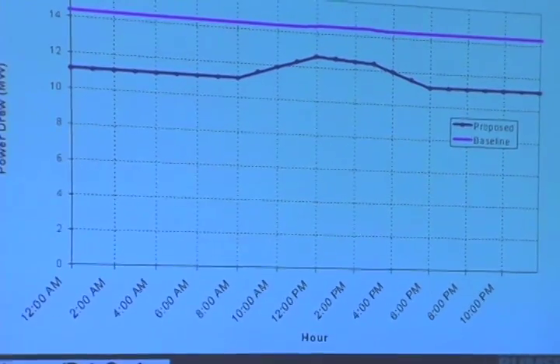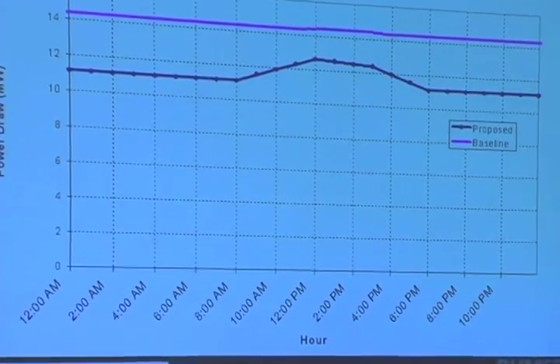Going back to the chiller energy model, the graph you had, did you look at chilled water storage or ice storage to use off-peak power for the cooling? So the question was, do we look at chilled water storage for off-peak or for failure? We did not look at that for a couple reasons. One is for off-peak, if we take the peak, which is, depending on how you look at it, 6 hours or so, and wanted to do 6 hours of storage, it's well over 1 million gallons. So it's quite a large tank.